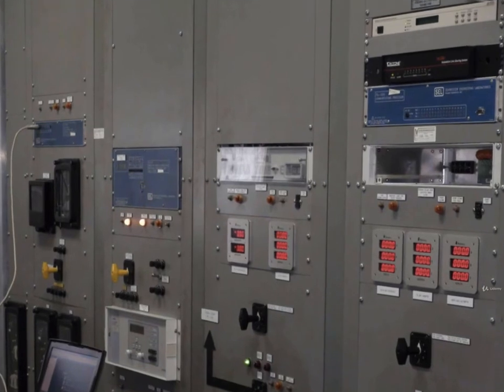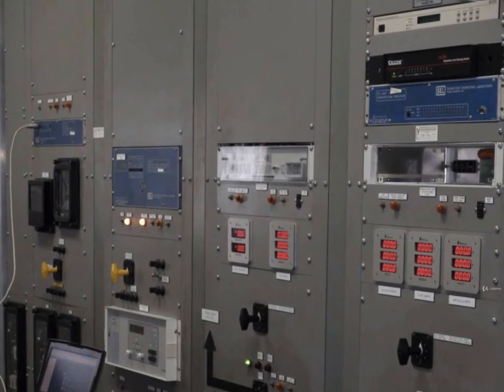An intelligent electronic device, an IED, is a term used in the electrical power industry to describe microprocessor-based controllers for power system equipment. IEDs receive data from sensors and power equipment and can issue control commands, such as tripping circuit breakers if they sense voltage, current, or frequency anomalies, or raise and lower voltage levels in order to maintain the desired level. Included in the realms of IEDs are the modern protective relaying devices.